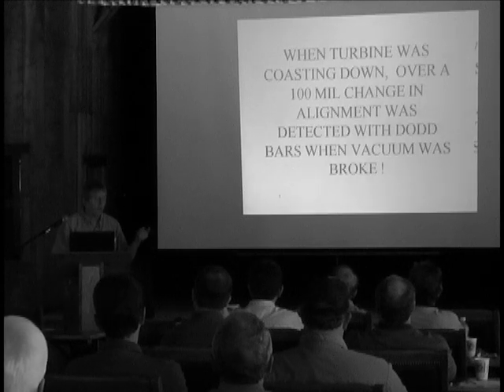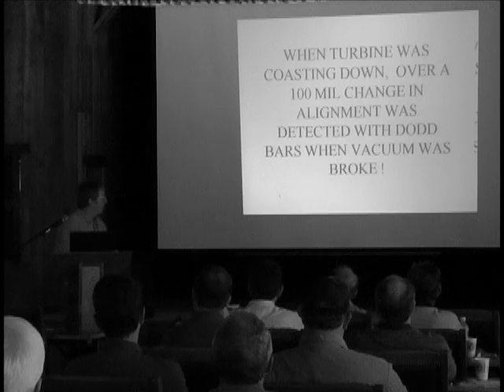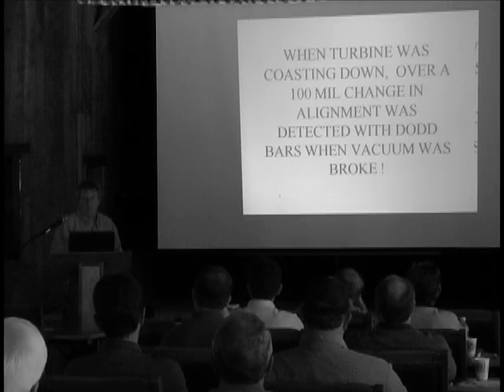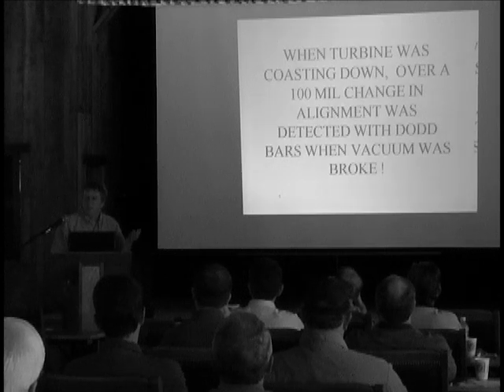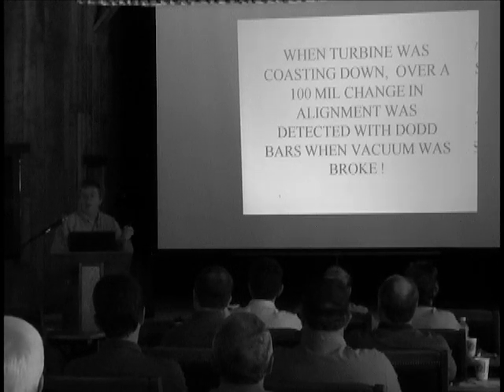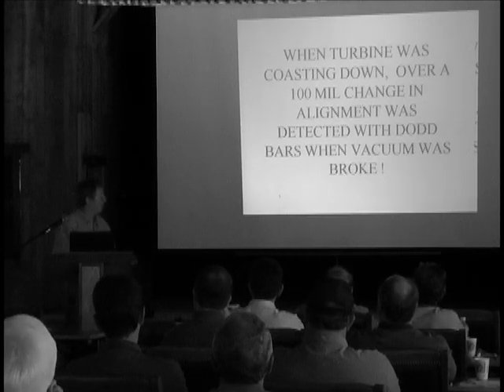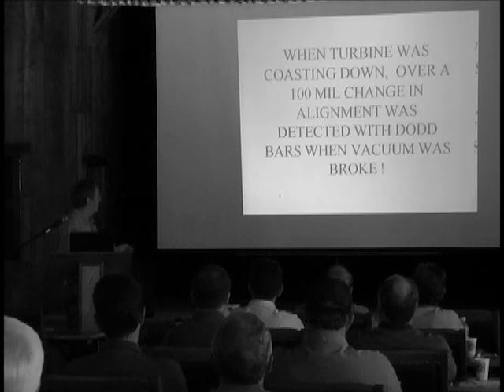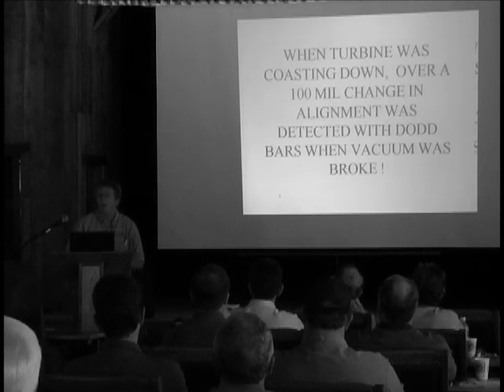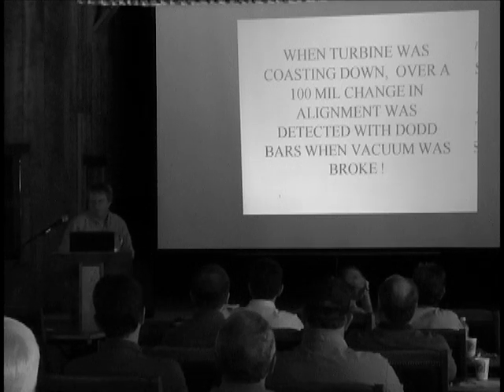And I had long-range probes. I had 120 probes that were 100 millivolt per mil. So when I went out there, they were jammed against it. I go, whoa. So I had to re-gap them so they could take it. Then I had them pull vacuum. I was getting a 100 mil change in alignment when they pulled vacuum on the turbine.